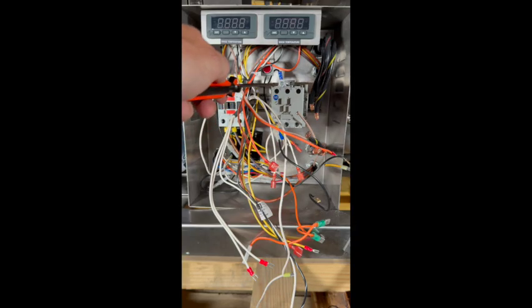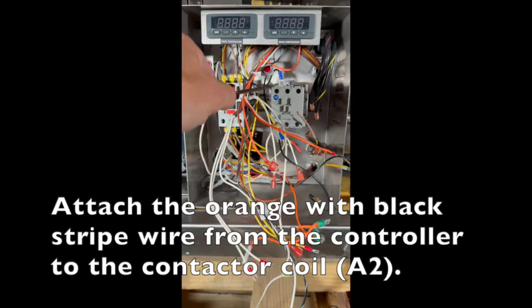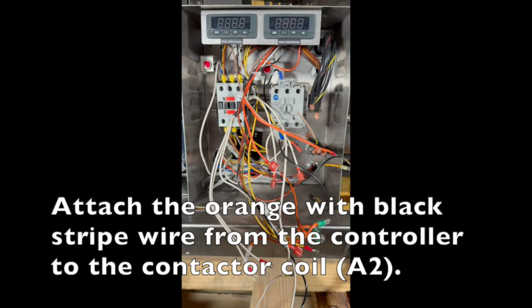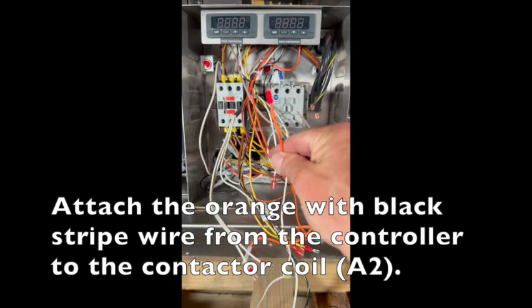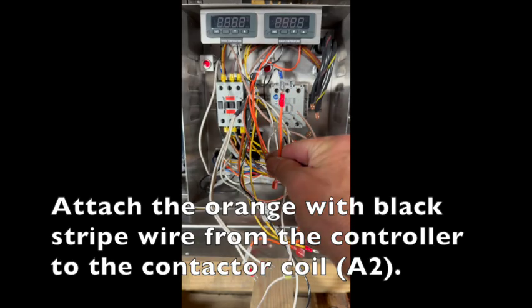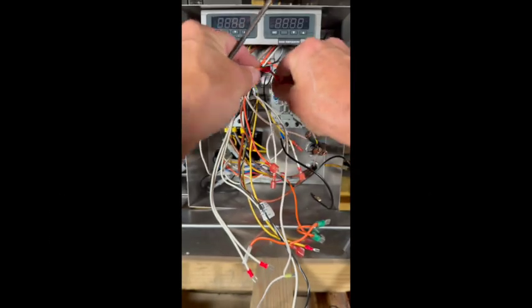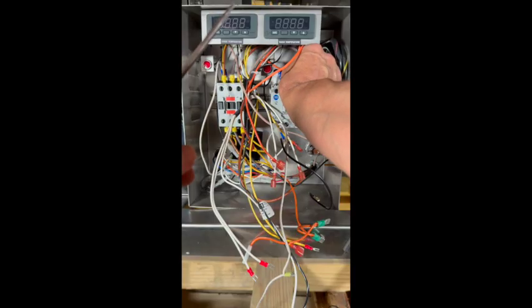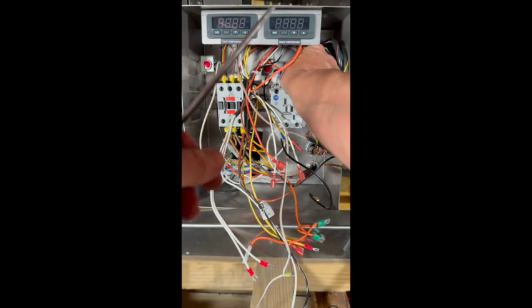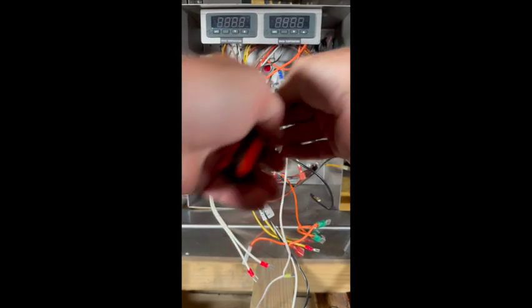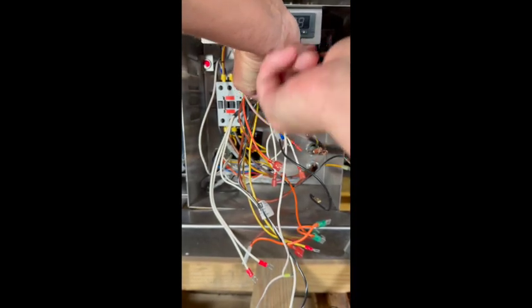Now here I did remove the heater wash element wires from that contactor just to make it easier to get to those coil contacts. So in the kit you're going to have the orange with the black stripe, and you're going to attach that to A2 on the coil of your contactor.